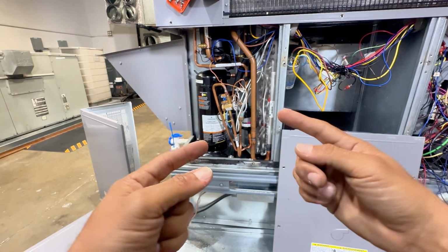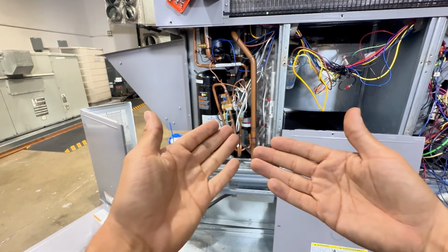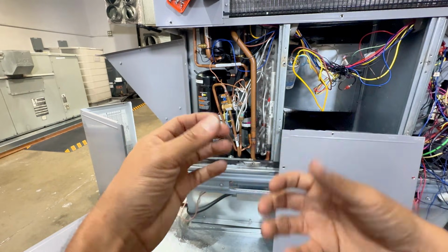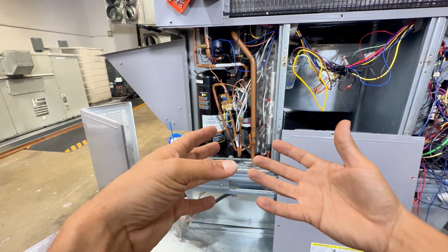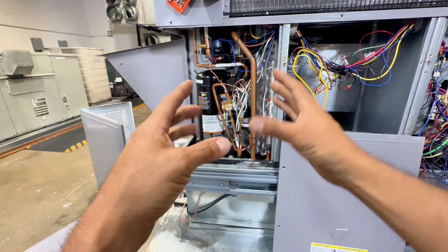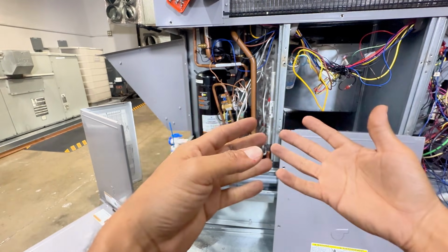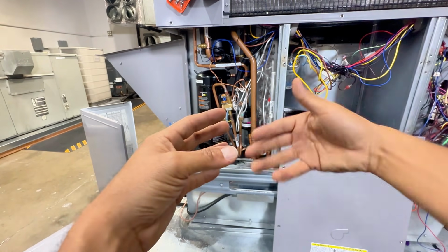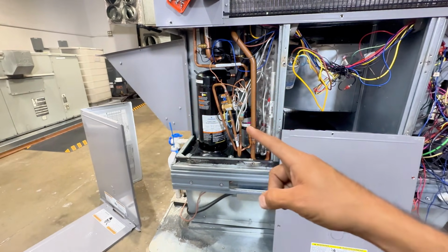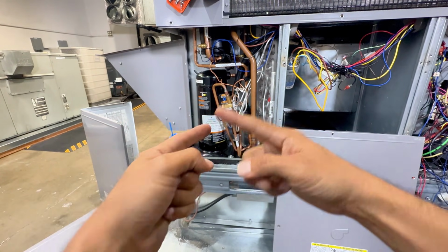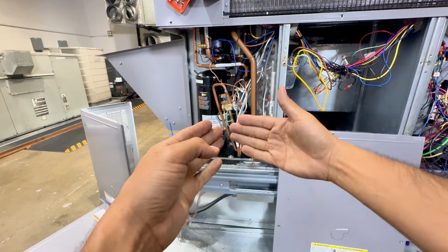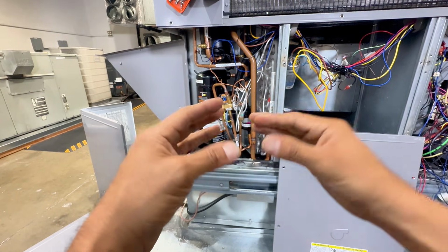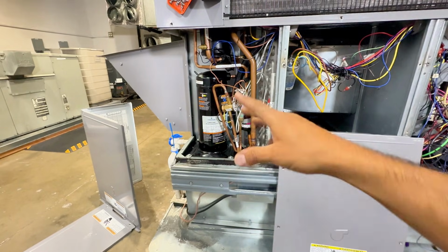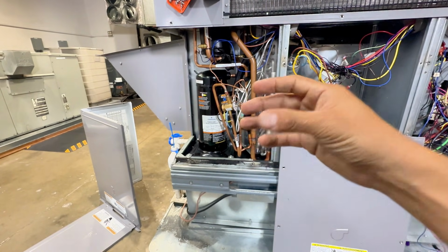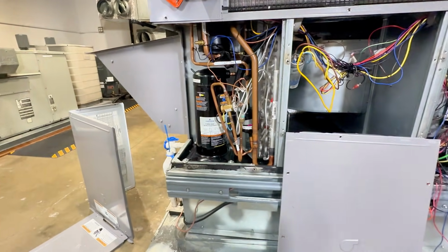But let's say now it's low on charge and you're pulling 4 amps or 5 amps. You're not doing a lot of work. So by just checking amp draw from a compressor, besides checking superheat and your charge, there's another way to find out what's going on with the compressor. You get the operating max, the rated load amps, and it's telling you it should be around here. And if it's not even close to that number, something is going on.